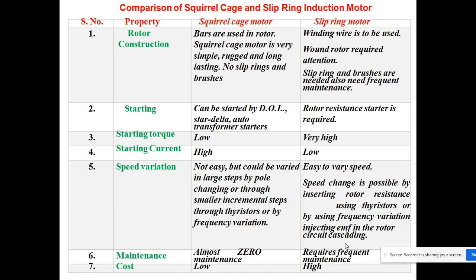Now I want to discuss the comparison between the squirrel cage and slip ring induction motor. We are doing the comparison based on seven parameters, starting with rotor construction. In the squirrel cage we use copper conductor bars. The squirrel cage motor is very simple, rugged and long lasting. No slip rings and brushes are used. But here in the slip ring motor the winding wire is used, the rotor requires attention, slip rings and brushes are needed, and it also needs frequent maintenance. So this is the comparison based on rotor construction.